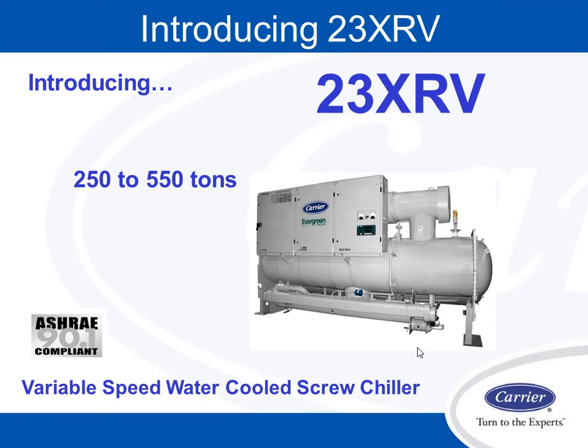Mainly, Carrier has now introduced what we call the Q compressor. What the Q compressor is, we basically have it starts from 250 to 400 tons, and then 400 to 550. Previously, we had one compressor that handled from 275 to 550, where 400 to 550 was a sweet spot. Below that was still very good efficiencies, but it could get better, and that's why we introduced the second compressor in this machine.